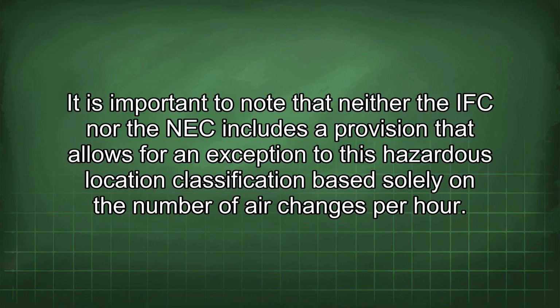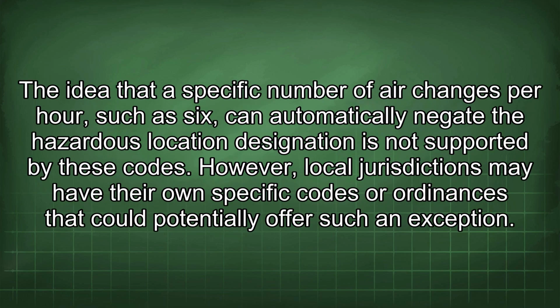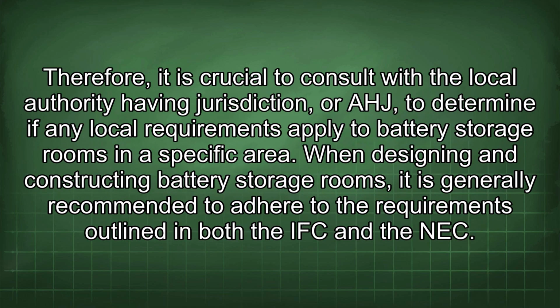It is important to note that neither the IFC nor the NEC includes a provision that allows for an exception to this hazardous location classification based solely on the number of air changes per hour. The idea that a specific number of air changes per hour, such as 6, can automatically negate the hazardous location designation is not supported by these codes. However, local jurisdictions may have their own specific codes or ordinances that could potentially offer such an exception. Therefore, it is crucial to consult with the local authority having jurisdiction, or AHJ, to determine if any local requirements apply to battery storage rooms in a specific area.